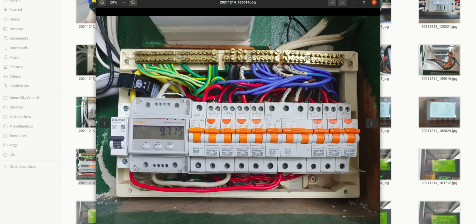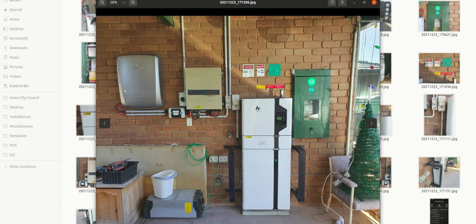Downstream, it's not affected by any power export, import, what have you, from the other system upstream from it on the grid side. So as far as this kilowatt hour meter is concerned, this could be in the next door neighbour's house. I think they want an EV charger now. Yeah, they want an EV charger.